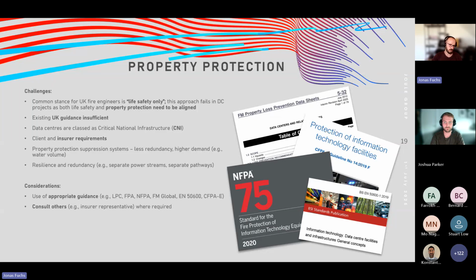So typically when you see certain pathways, you will see that there are fire resistant construction separating separate cable paths serving, for example, data halls. Each data hall is typically its own fire compartment, and typically if you've got interior electrical rooms, again, high degree of compartmentation. If you've got exterior transformers and they're in close proximity, you will often encounter a firewall construction between the transformers. So to counter and prepare for any property protection requirements, ensure that you use appropriate guidance that's available from industry bodies such as LPC, FPA, NFPA, FM Global, EN series of standards, and CFPAE, and then obviously consult everyone on the project team, especially client representative as well as insurer representative.